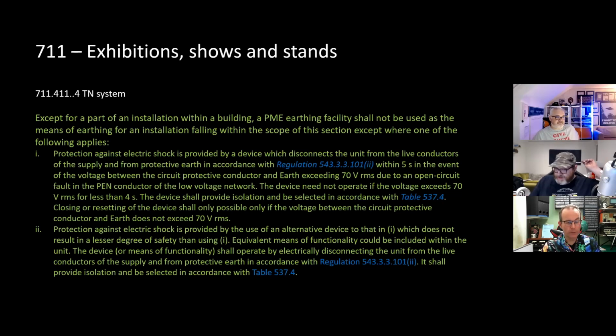They're Teflon-ing onto the homeowner and the installer, and it's not fair. And Andy says, any clarity on whether 7909 applies, and what about TNS stop being TNS? Well, 7909 doesn't—there's not a clear line as to what is 711 and what is 7909. There's some good interpretation about it. I think probably one of James E's books puts it best, where he tries to explain the difference between an event and just a work exhibition. The way I think about it is 7909 has to be read in line with 7671. It says right at the beginning of 7909 that this must achieve full compliance and coordination with the fundamental principles of 7671, and the fundamental principles of 7671 will push through to part 7 to supplement the rest. So in my view, I'll comply with BS7671, and then if necessary, I'll then add to 7909.